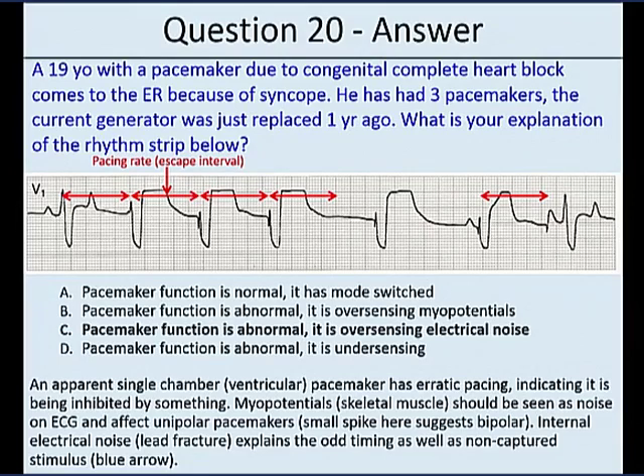More likely it's a broken lead, and as he has micro movements, just respiratory movements or so, a lead that is actually the metal is fractured, but has come back together, so it makes contact most of the time, just like a lamp cord or a radio cord can have static in it. And occasionally it breaks apart and then comes back, and when it comes back together, there's a little static there. It makes a signal. The pacemaker sees that as a genuine ventricular event, says, I don't have to pace. So it waits until the next interval to pace. And so this guy has a lead fracture, and this is actually a case that ended up with a very tragic outcome. This was from a monitor, and it was read as being normal, and so the patient's caregiver said, okay, everything's normal, I guess, and he ended up having syncope and a cardiac arrest without escape and did not survive from that. That's a pretty bad outcome.